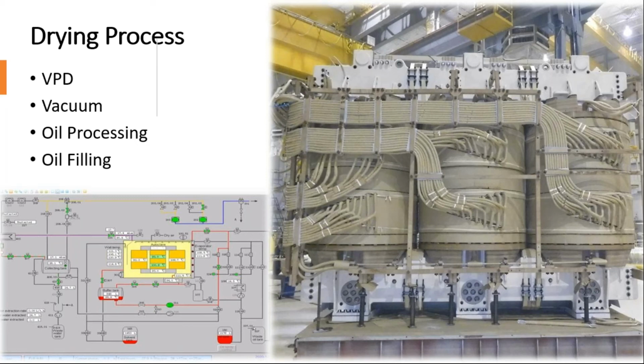So the way vapor phase works is, the whole process of drying happens in a vacuum chamber, and the media which is used for convection, for the heat transfer, is vapors again. So the process happens under vacuum, under heat, temperature pretty much 110, 120, it can go up to 130 or 140 degrees Celsius. So it is an accelerated extraction of moisture. And this process can easily extract moisture up to 3-4 inches thick pre-compressed board, or high density pre-compressed board, without any issue.